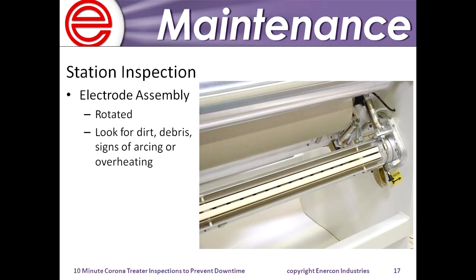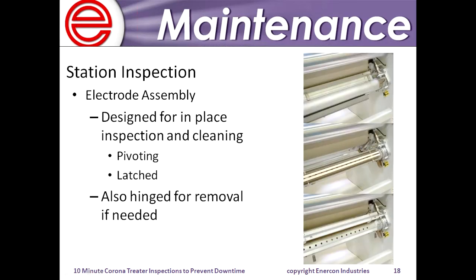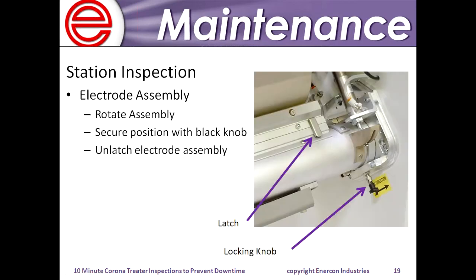Look for any obvious signs of damage or dirt or anything like that on the electrode surface. And one thing that we have, on any of our systems in the last 10 years or maybe slightly longer, is a convenient hinge designed to hinge that electrode assembly open, so you can expose the underside of that, the cooling air ports. And the next few slides will outline how to hinge that electrode assembly open the proper way.